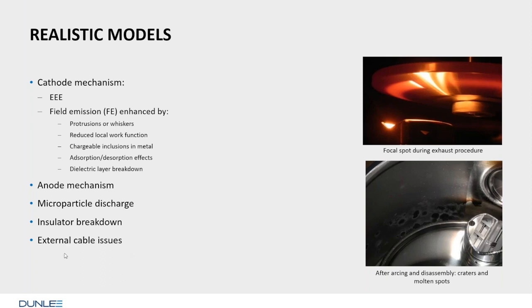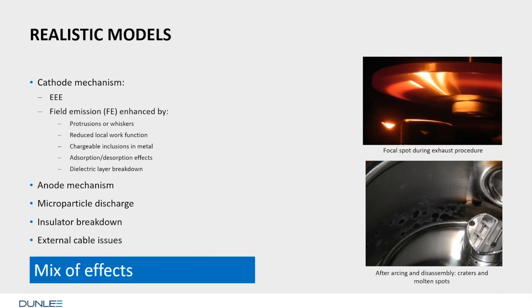So this is a series of models which are most probable. It's a mixed effect often. Sometimes the tube starts with a cathode mechanism, then experiences also microparticles, because after a discharge, particles are released. An insulator may be deteriorating, and again, also from all these events and so on. So it may be a mix of effects even in a single tube.